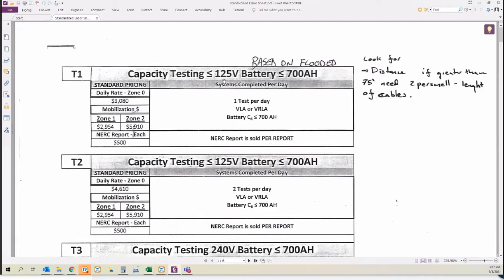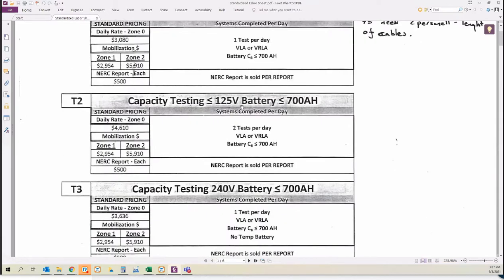So a cap test, less than 125 volts and less than 700 amp hours, that was correct, 700 amp hours is the cutoff. You do one test per day. If it's less than or equal to 700, we can do two tests per day. What it doesn't show you here is that it added the extra 4 hours we talked about.